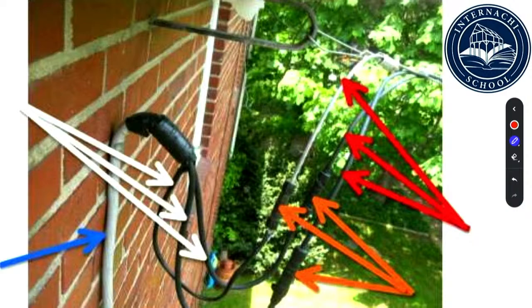That's where some of these lines come in. These are the power lines, also known as the service drop - that's the red. The orange are the connections, I refer to them as the splices, and that's the line in the sand. Anything on the pole side of those splices belongs to the electric company. Anything not including the splices that goes toward the house belongs to the homeowner. The white is pointing at the service entrance cables, which come down to our meter and into the house. This is an old gooseneck they're pointing at, and the service mast is what the blue arrow is pointing at.